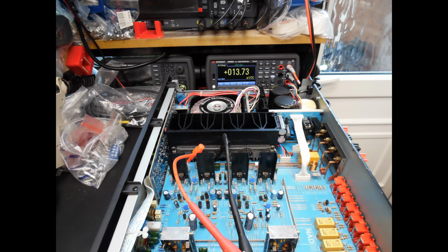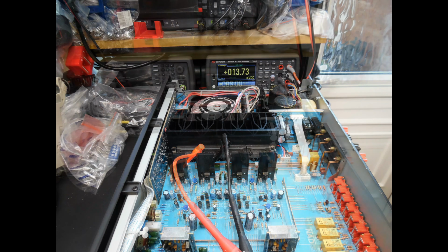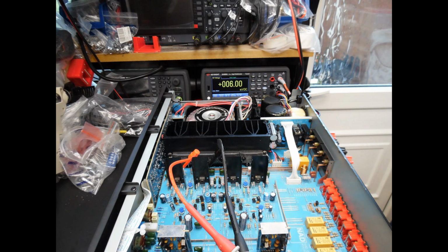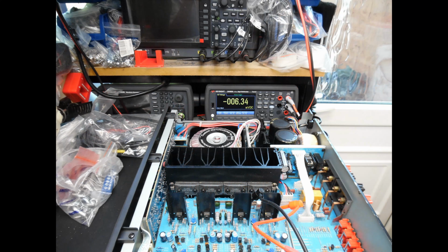Here what you can see is that this channel is high. It's 13.73 millivolts. I need to make the adjustment as we say, and then here what I've done is I brought it down to 6 millivolts, which is within the range as specified in the service manual. But then when I did it for the other channel, to make the initial measurement, it didn't require any adjustment at all. It was 6.34 millivolts. And as I said, in terms of adjustment for this amplifier, it's very, very easy to do.